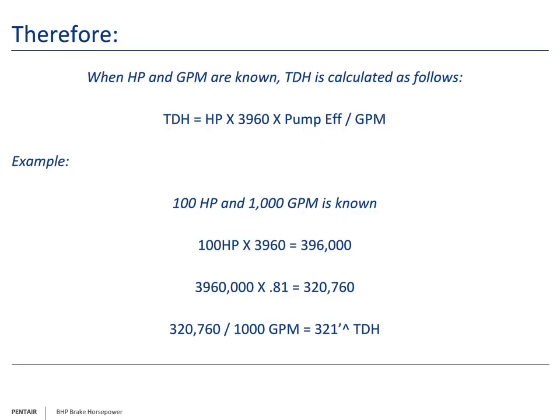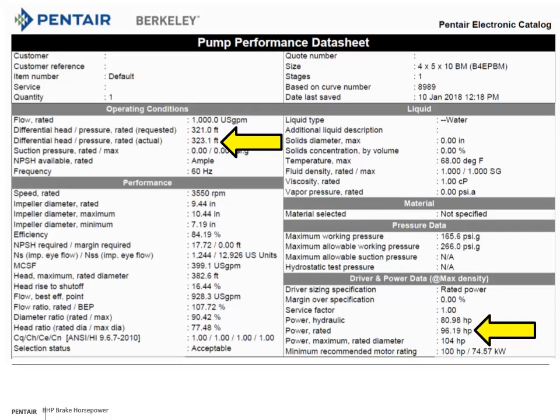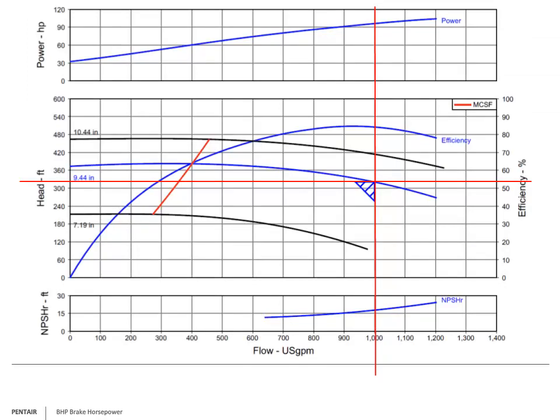This then gives you the information to do a deadhead test of the pump. Now, granted, the information has been given to us, and we have been able to calculate the head easily. Now let us take the opportunity to use a sizing program and pull up a curve. Reviewing the curve, you can see we are spot on. Will the data given guarantee this is in fact the submersible pump curve of the pump we are testing in the well? No, but we have gained two pieces of information. The first, the total dynamic head to test the pump, and second, the parameters we need to size a new pump should we need to.